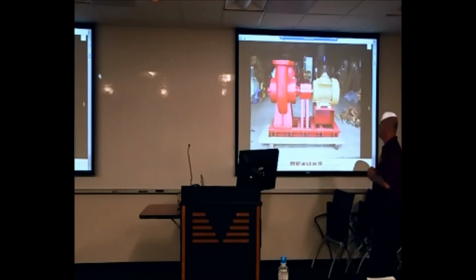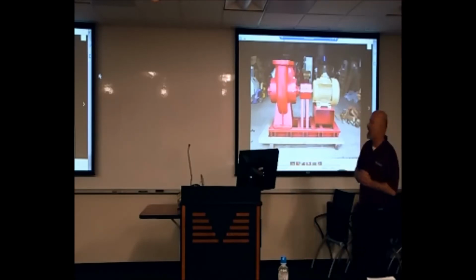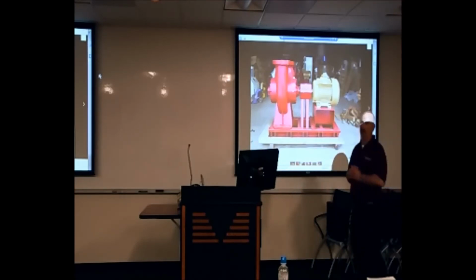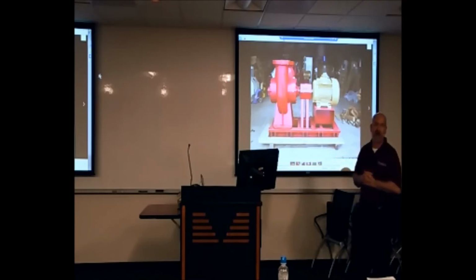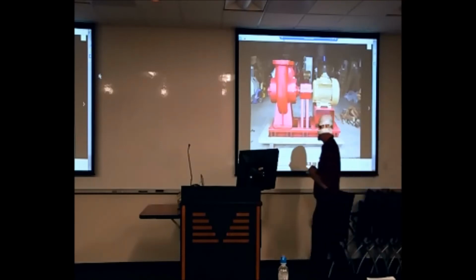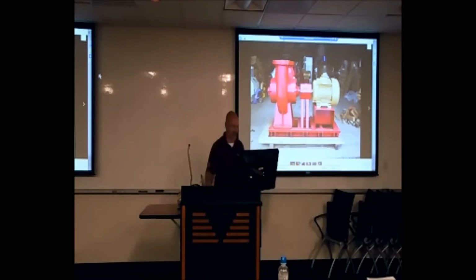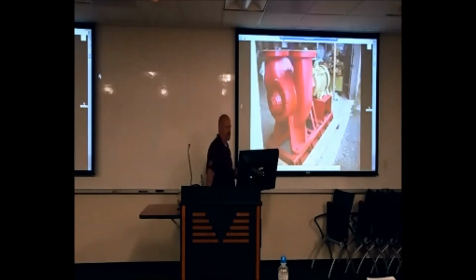And then probably the last thing on these is air. Cooling towers are notorious for getting a lot of air through the pumps. If you ever notice that you're shutting off pumps for extended periods of time, sometimes air will get in the top pocket of the pump. I usually would recommend bleeding that air off or putting an air vent on that location. Let me see if I've got a nice picture. There we go. So we've got 2 little connections right here at the top of the pump. You can see my little cursor circling around those.